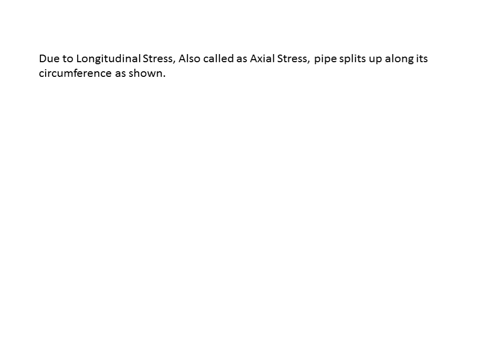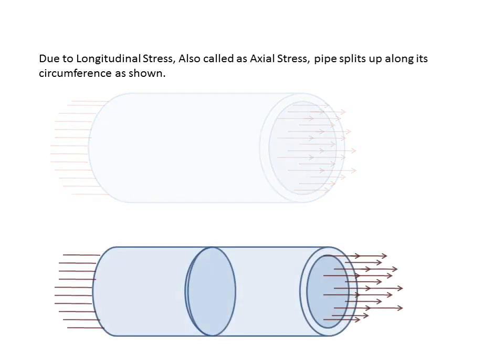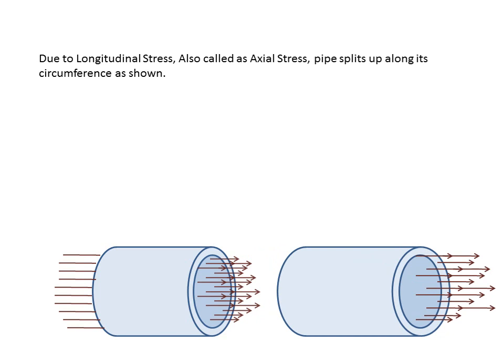Due to longitudinal stresses — also called axial stresses — the pipe splits up along its circumference. If the pressure is too high, a vertical split will occur, leading to failure and damage of the pipe. An image of the axial failure mode is shown.